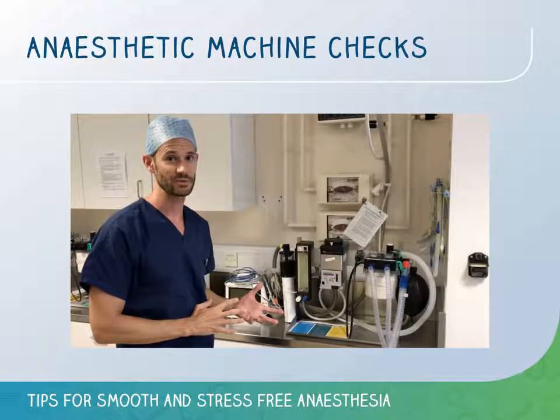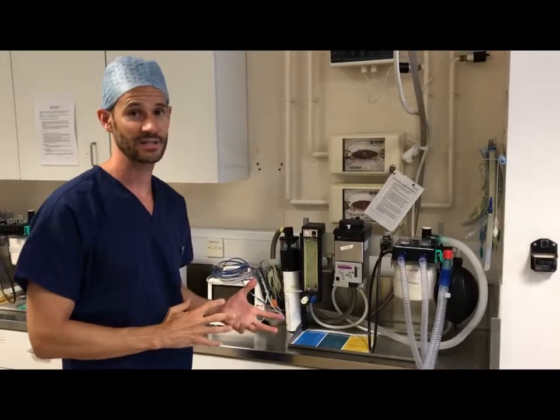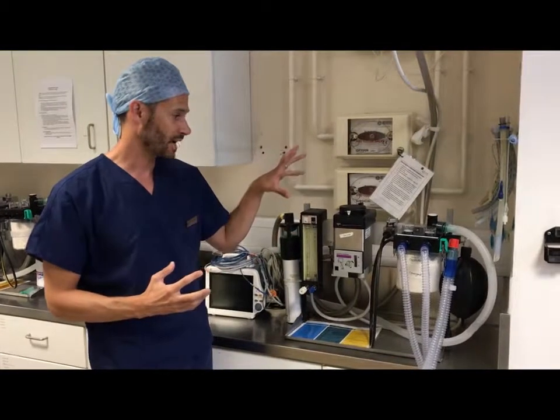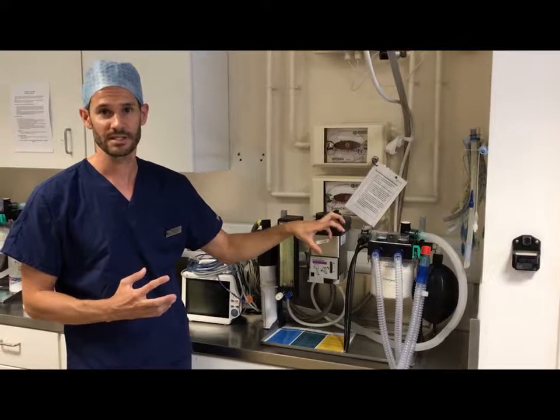Let's take some time out here. Before we use our anaesthetic machine, we'd better check it. Okay, so we're going to do a quick video on how to check an anaesthetic machine. And the three things I'm really looking for are, I'm looking at our oxygen supply, I'm looking at our volatile agent supply, and we're going to check the integrity of our breathing system.